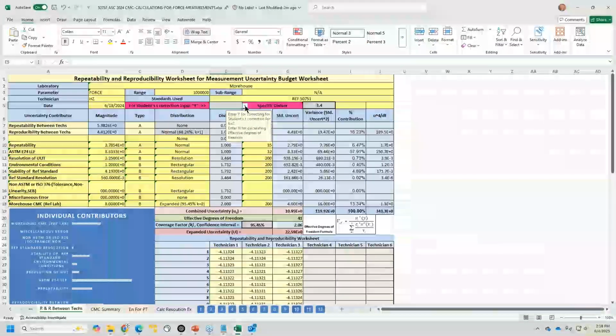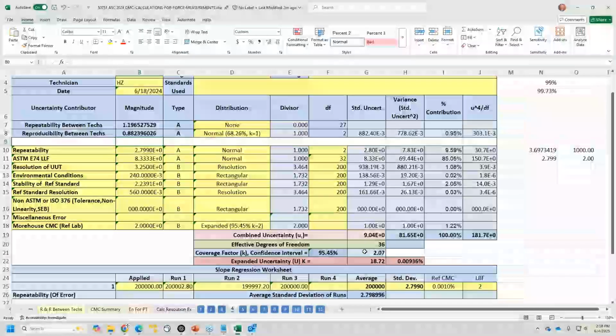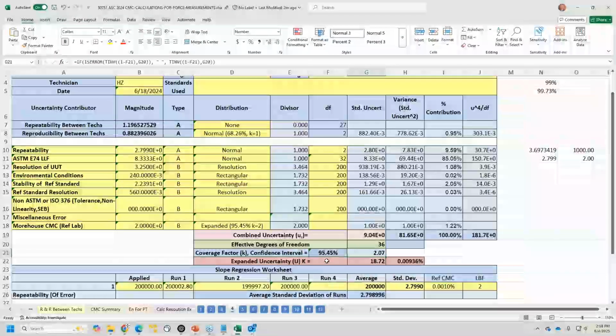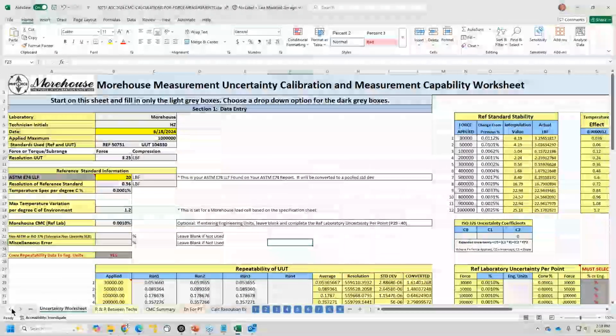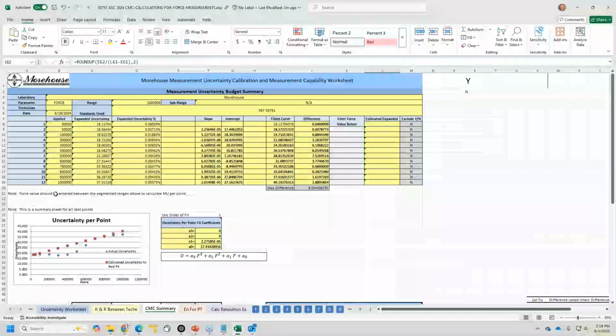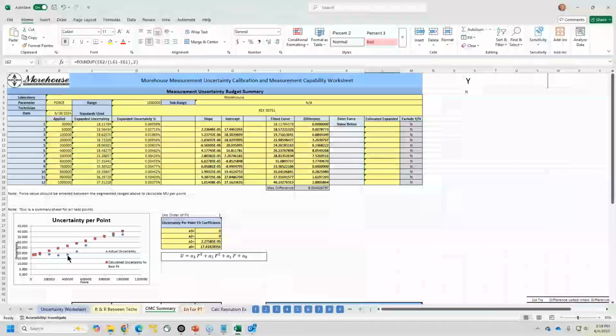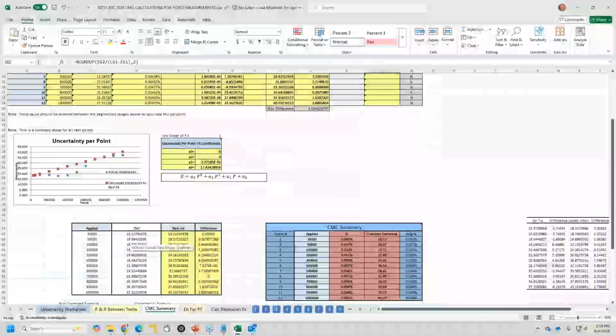Like if you have low repeatability, you can convert everything so it equals way beyond this course here. But look at my coverage factor, 95.45% is what we're using on this. If I wanted, I could change that to 95% actually. But if I go to the summary sheet here, this basically says it's filled out. There's my actual uncertainty and my uncertainty per point. And if I want to give A2LA a nice little formula, I'm probably going to over-report my uncertainty in some of these cases because I have to fit it.